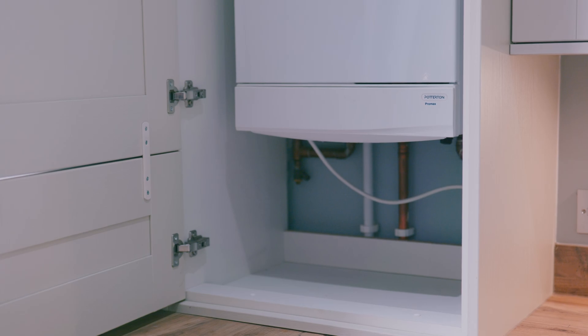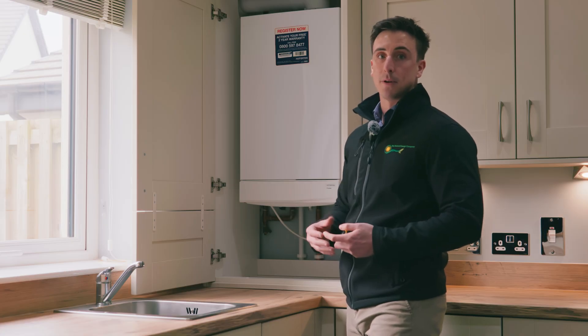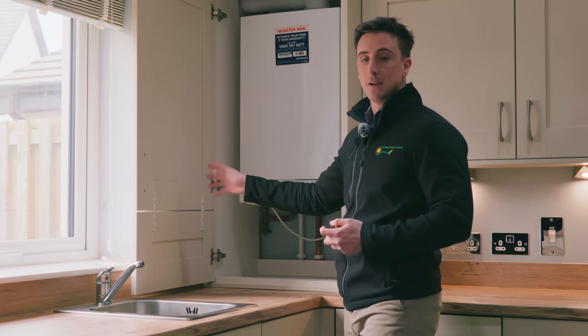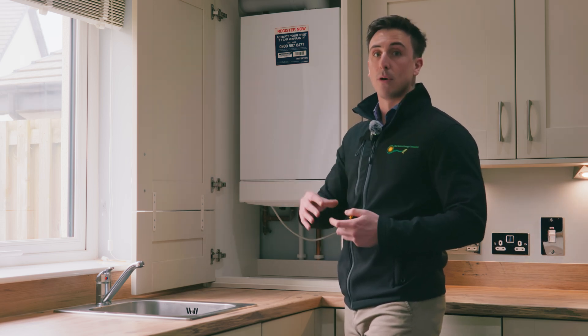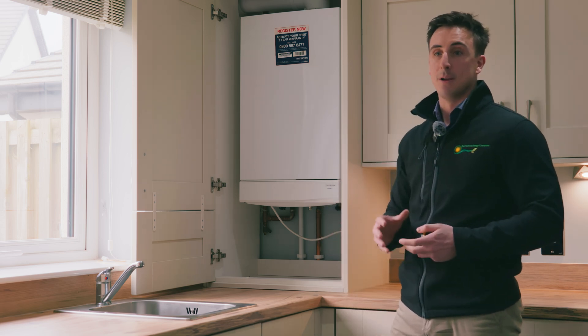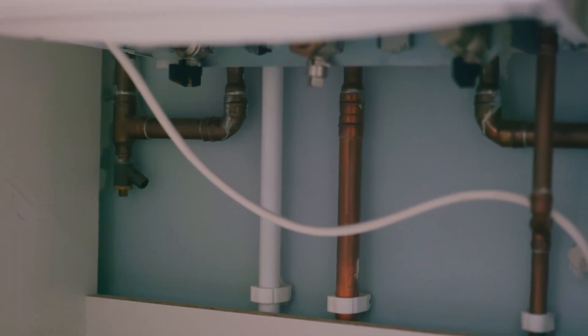You've also got on this boiler some pipework which isn't quite suitable for a heat pump. The typical heat pump pipework needed to take energy from the outside unit to your radiators or the hot water cylinder needs to be around 28 millimeters, and most houses from their boilers will be around 22 millimeters, which is what it is in this case.